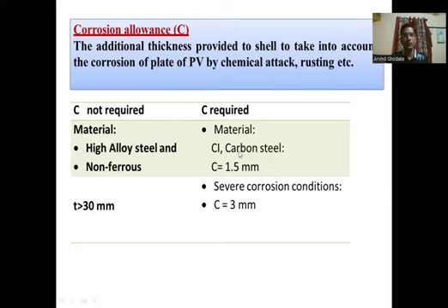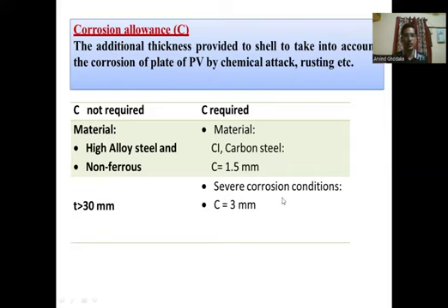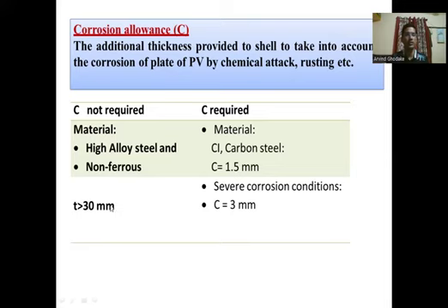If the material is cast iron or carbon steel (with a higher percentage of carbon), a corrosion allowance of 1.5 mm is considered. If the pressure vessel thickness is greater than 30 mm, no corrosion allowance is needed for any material. However, if the material suffers from corrosion conditions, a corrosion allowance of 1.3 mm or 3 mm is applied.